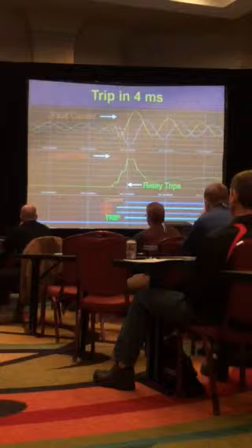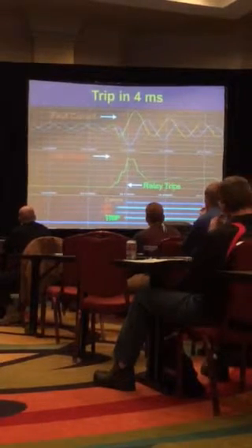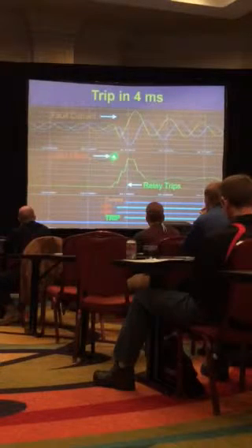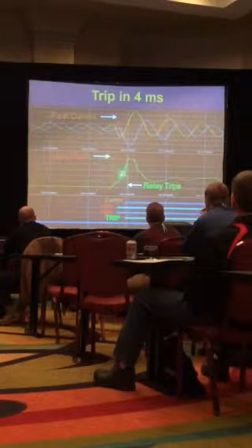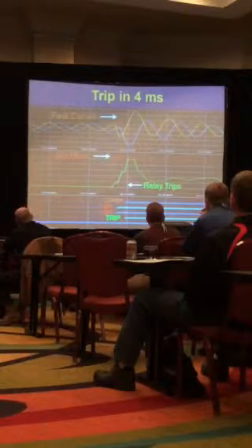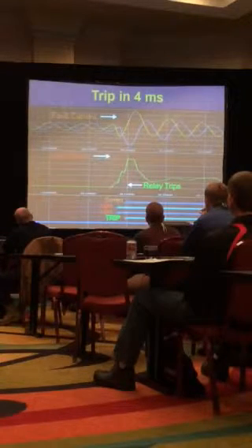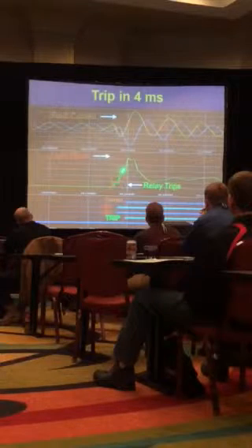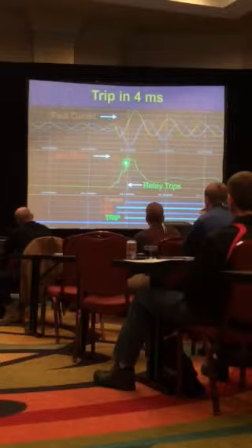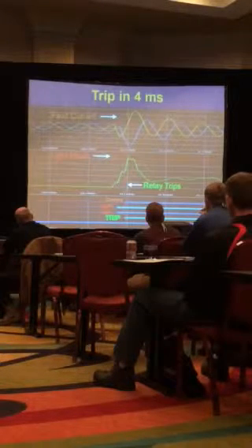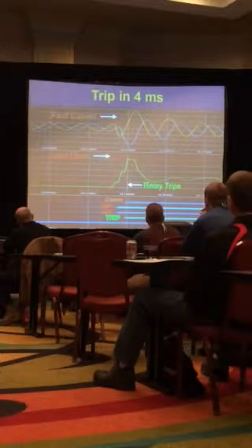How's it work? What's cool here's the current, and you can see the fault current jumping up on a couple of phases. And the next trace here shows the light flash, that red line going up. And this yellow line on the middle one, that happens to be where the relay is determining the magnitude of the current. So by the time that there's enough current and light, put those into an AND gate, and we're getting a trip command to the breaker in 4 milliseconds.